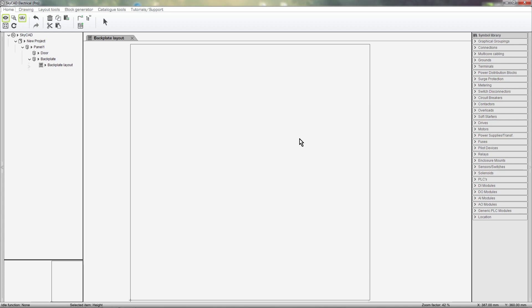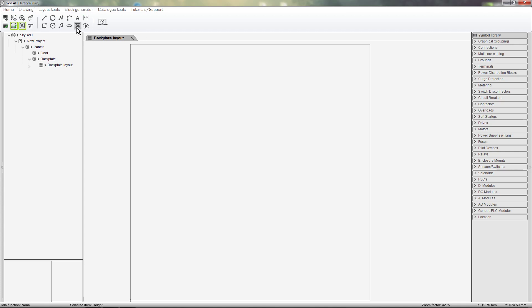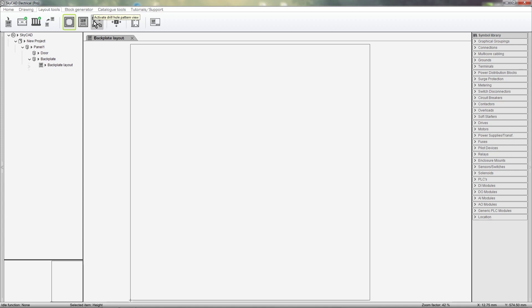To define a layout, we do this in the same way we would for defining a layout for any other component. We can either draw our backplate using the drawing tools, or we can insert an image of the backplate from our computer, with the exception of activating the Background View by clicking on the Layout Tools tab and selecting Activate Background View. Let me explain a bit more about the different views available: Background View, Main View, and Drill Hole Pattern View. These views are similar to layers but for specific purposes. The Main View is where all the laying out of components, DIN Rails, and wiring ducts takes place — this will be the view that is most often worked with.